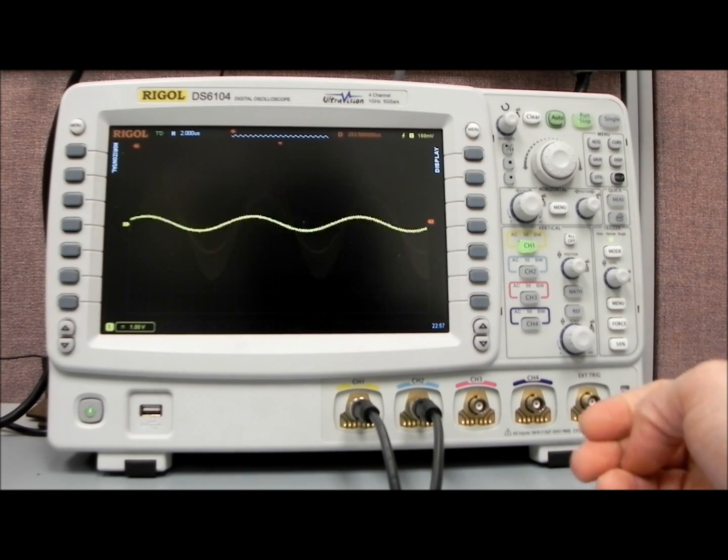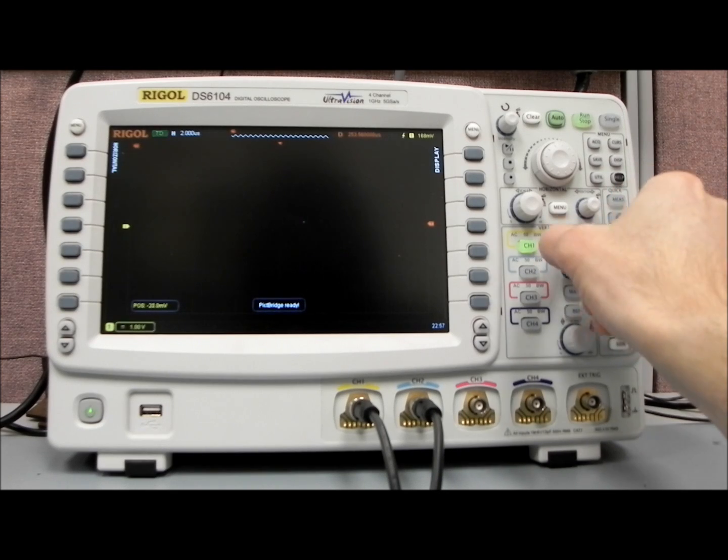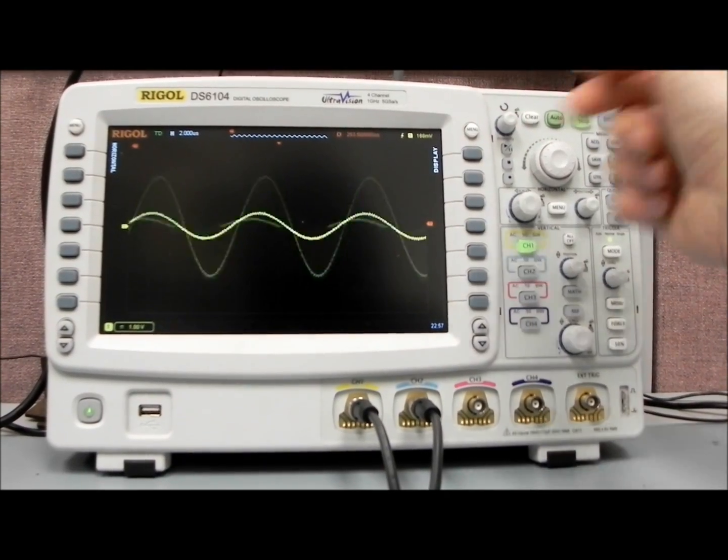And it's going to stay that way as long as we don't move any of the waveforms. As soon as we move the waveform, it's going to automatically overwrite everything, clear the display, and then start back over again.